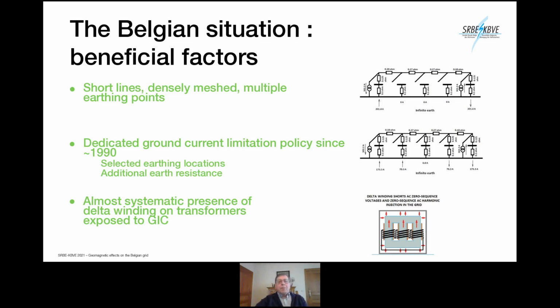But this policy was done by selecting earthing locations, removing as much as possible earthings where not needed, and putting in additional resistance in the earthing points. And this has allowed us to reduce further the currents of the example 2 by a factor 2. So we are no longer at 250 amps, but only at 70 amps or something, a factor 4. So, which is important, of course.